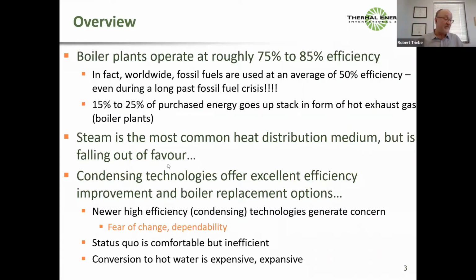So the overview, you guys all know this: boiler plant 75 to 85% efficient, 15 to 20% goes up the stack. Worldwide, fossil fuels, if we look at the old days of power generation at 35% efficiency and boilers at 80% efficiency, during the fossil fuel crisis, fossil fuels were used at an average of 50% efficiency, which is pretty crazy. Steam is the most common heat distribution medium, but it's falling out of favor because of inefficiencies we'll discuss as a part of this presentation. Condensing technologies offer an excellent efficiency improvement and boiler replacement option. They're newer high efficiency technologies, but there's some fear of change and dependability. Status quo is comfortable, but inefficient.